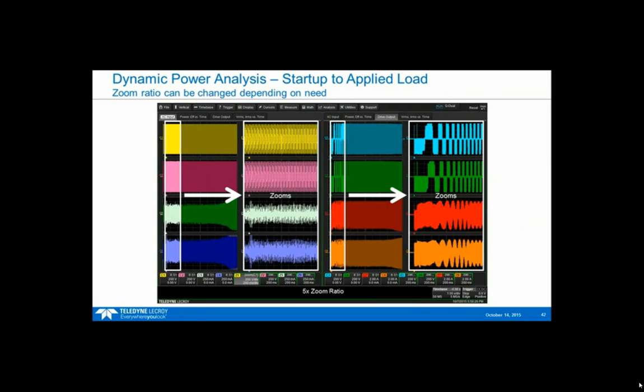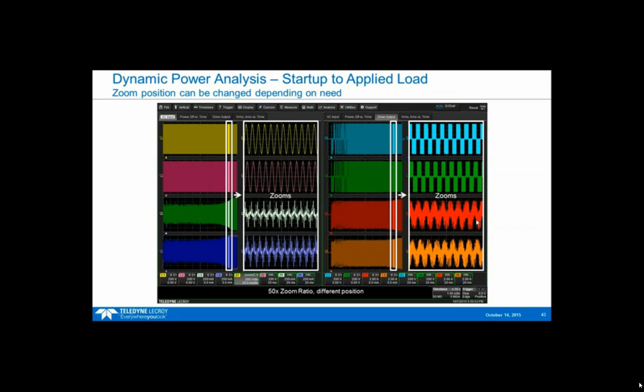I can change the size of the zoom ratio. Here I've made it a lot bigger, so I'm seeing more time in the zoom, and I can see my startup event pretty clearly: very low frequency, ramping up to a very high frequency on the drive for the voltage, and then my current period changes as well. Or I can change that zoom ratio to be smaller again and move it somewhere else. In this case, I'm seeing some behavior where the drive has reached very close to its steady state condition. You can see here I've clipped a little bit. The product does have the ability to read a little beyond that, but what I'm going to want to do here is gate the acquisition.